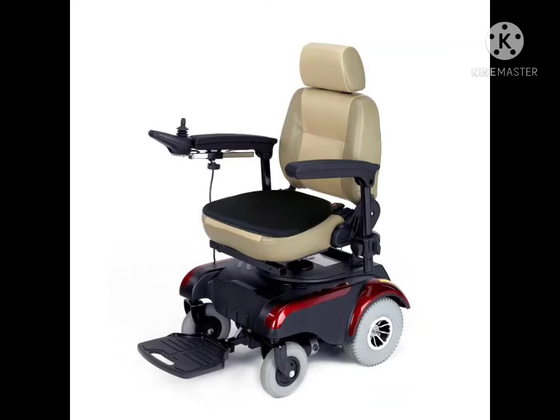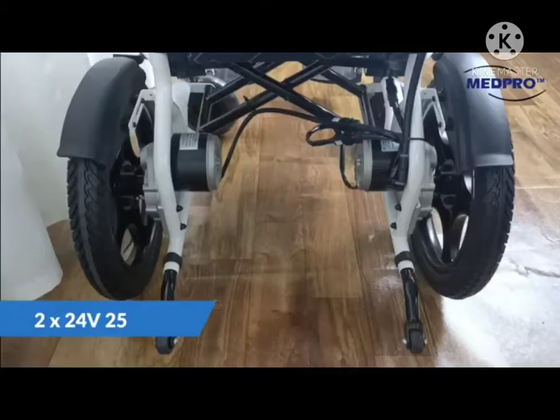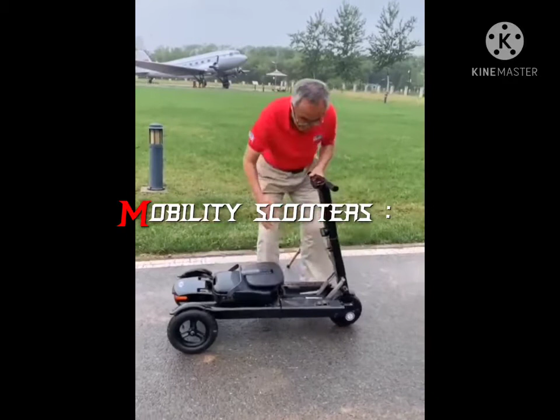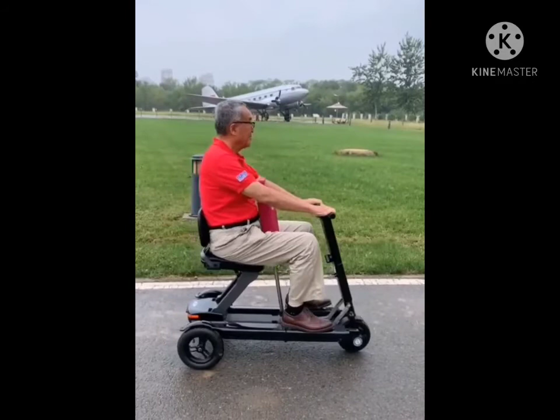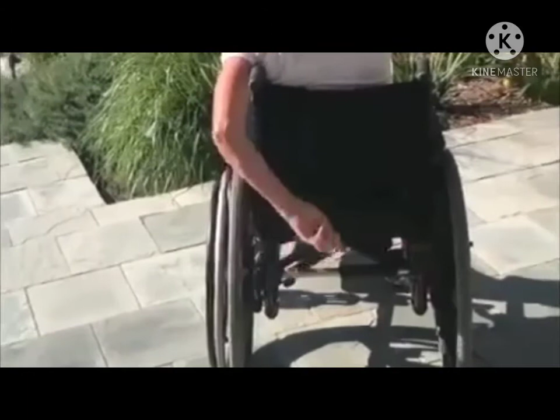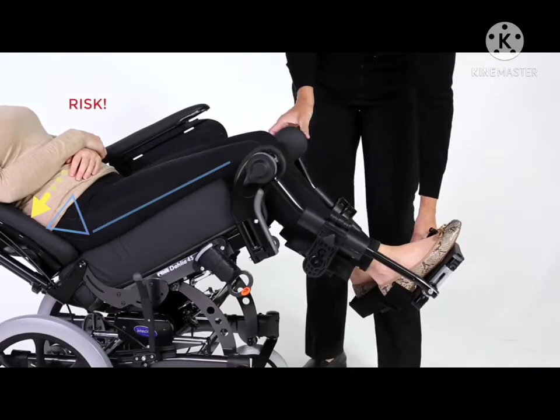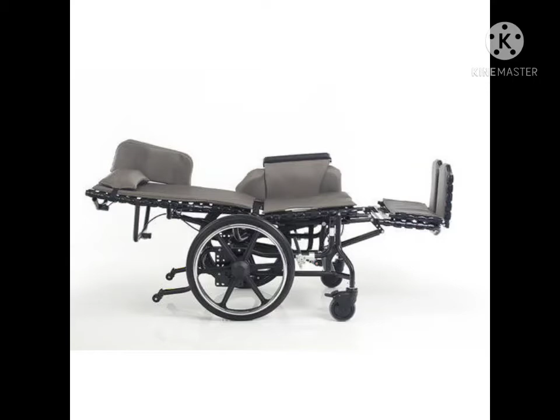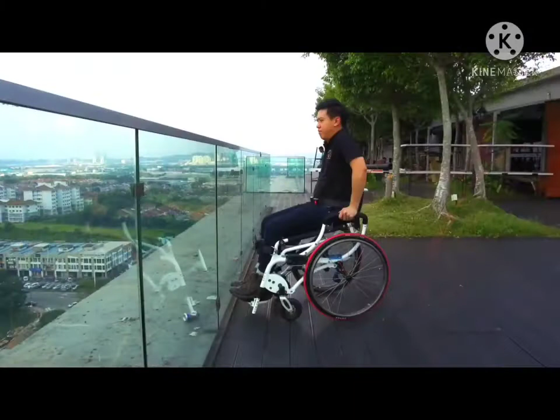Then in advance, lithium battery fixed electrical wheelchairs are for travel over a distance and dual motor is for heavy duty performance. And mobility scooters are for those having limited ability to walk. And the single arm drive wheelchair enables a user to self-propel a manual wheelchair using only a single arm. Then reclining wheelchair. This has a seating system which can be tilted to various angles. Good for persons who are unable to sit upright for extended periods because of pain or other reasons. Various designs are available, and wheelchairs with these features may either tilt the seat back and leg rests in relation to the seat, or may tilt the entire back, seat and leg rest as one, depending on the need of the user.